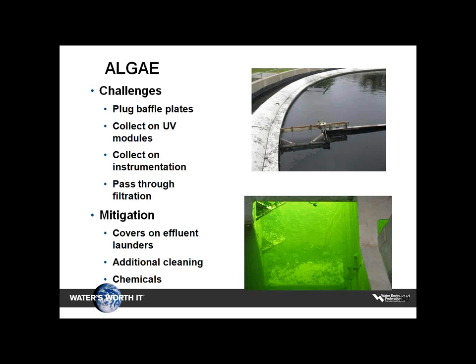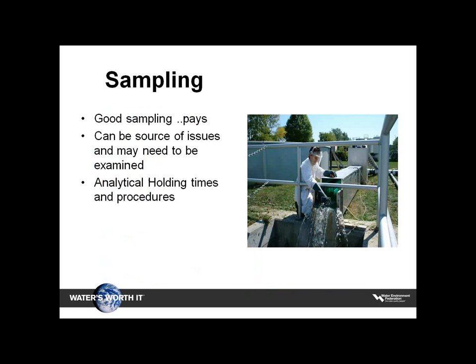I just hit a couple of operational issues. Algae is one of my favorite ones, and trying to keep it clean. Algae will tend to collect on the UV system, and then trying to get on and like covers that might be used to control algae.